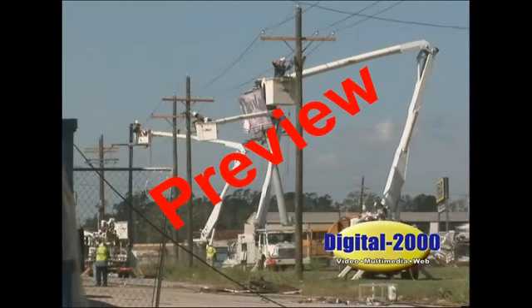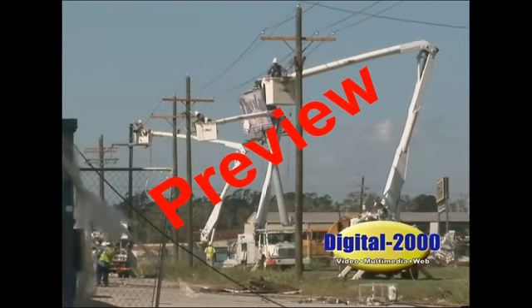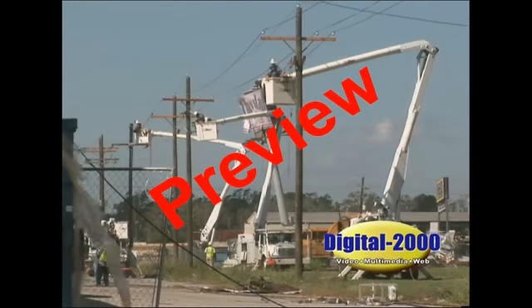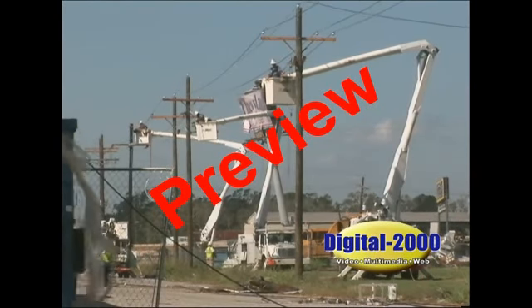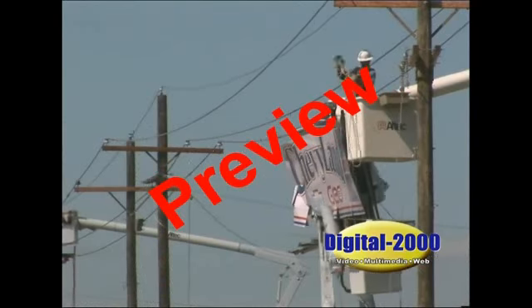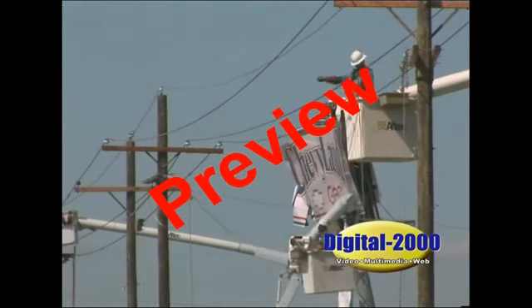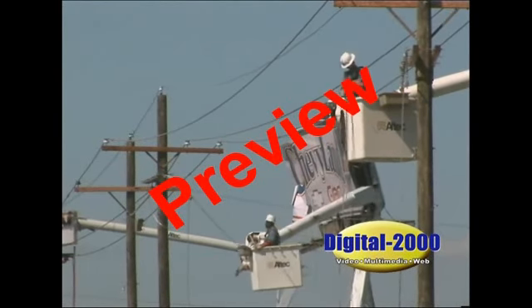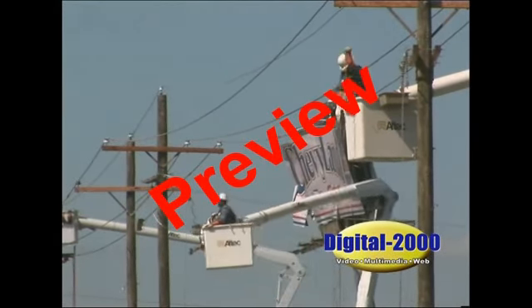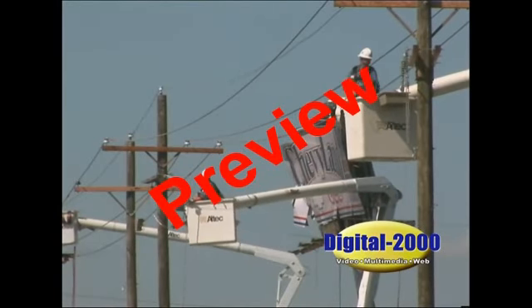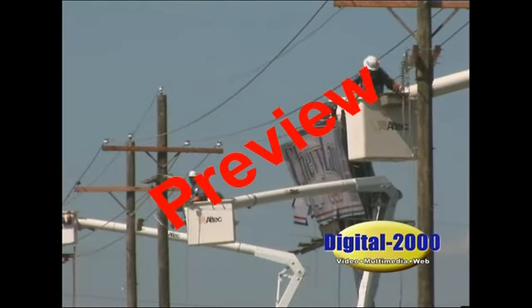The common distance used for most low-voltage incident energy research and testing is at 18 inches from the arcing fault source. If a person is closer than 18 inches, the higher the incident energy and blast hazard. In other words, if the body has sufficient PPE for an 18-inch working distance, severe injury can result to any part of the body closer than 18 inches to the source of the arc.